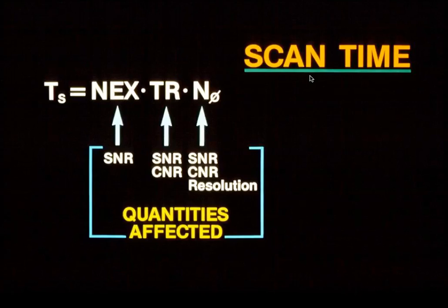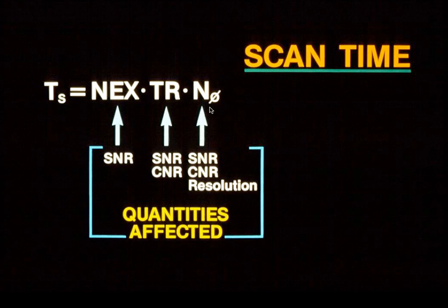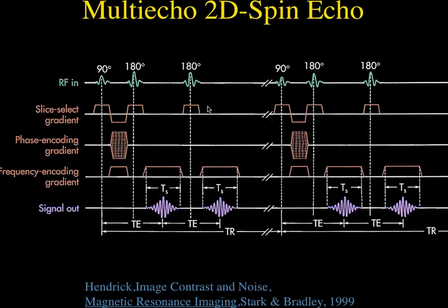The longer the T1, the longer we have to wait for recovery. Scan time with standard imaging is TR times the number of phase encodings. If you signal average, say two NEX, that doubles the amount of time, so it's NEX times TR times the number of phase encodings. It was recognized early on that maybe we could be more efficient if we got two images for the price of one.